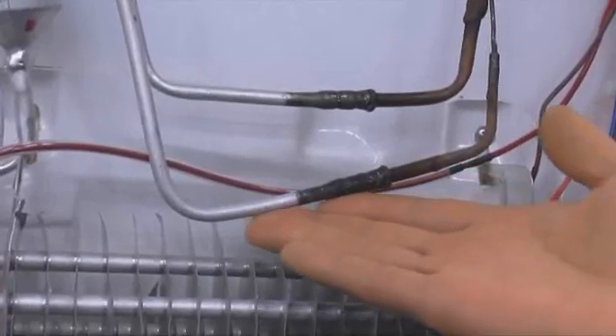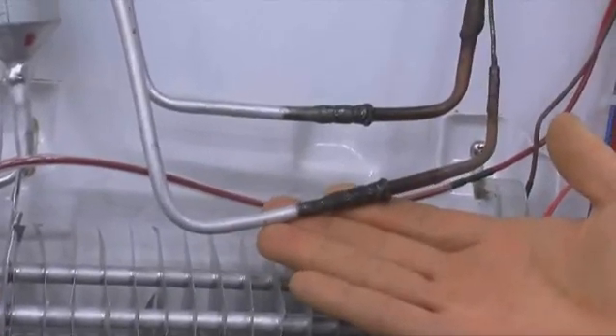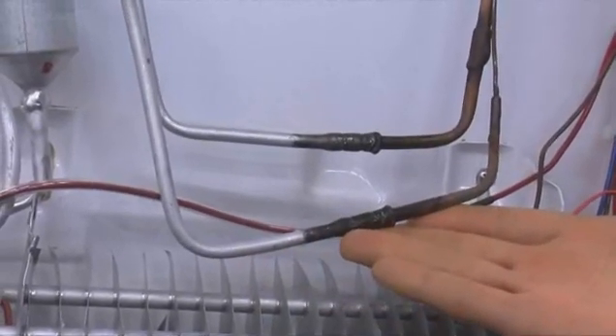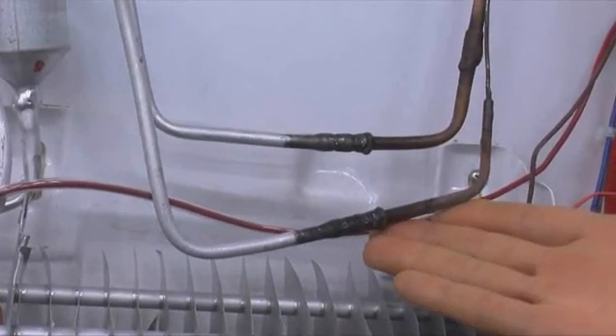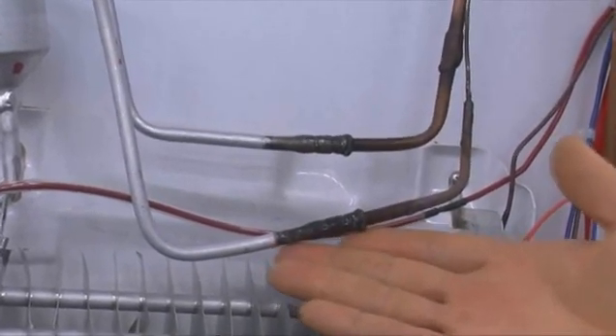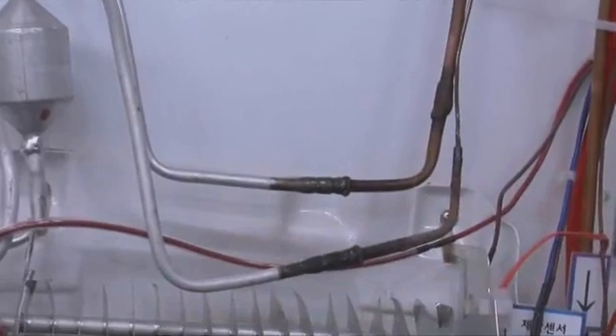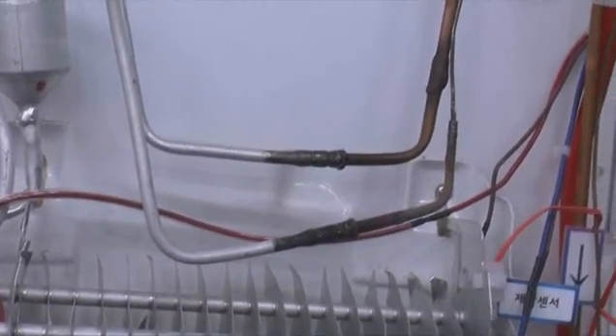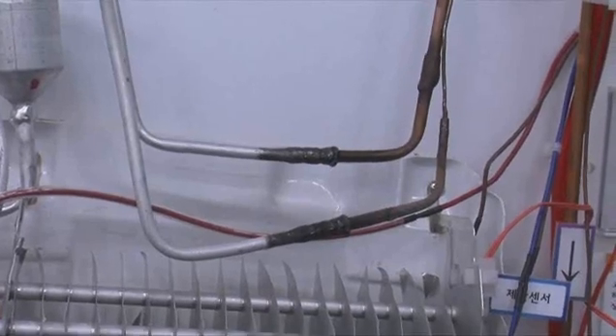If the evaporator is cold, it is normal — you can see frost forming. If the frost forms and feels cold, it shows that the gas is circling normally. After connecting the jig and operating the compressor for 10 minutes, if frost forms, we can determine the product is normal.